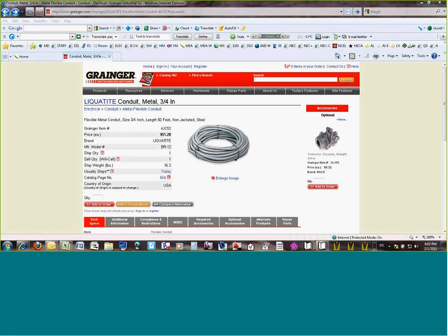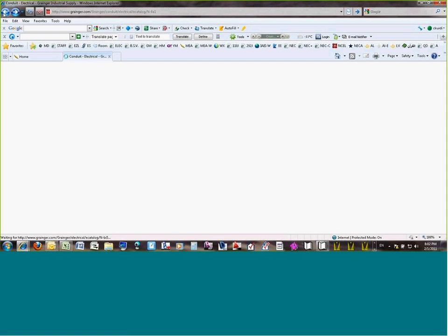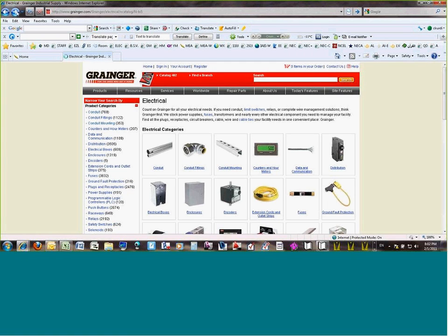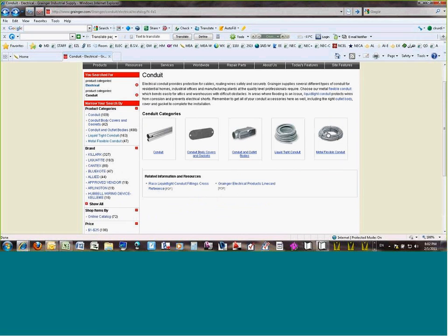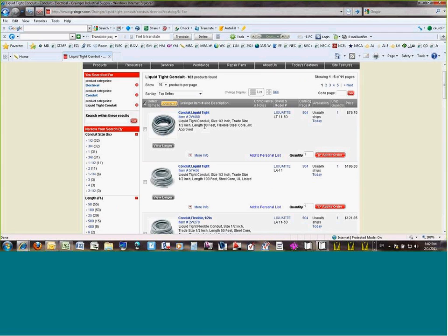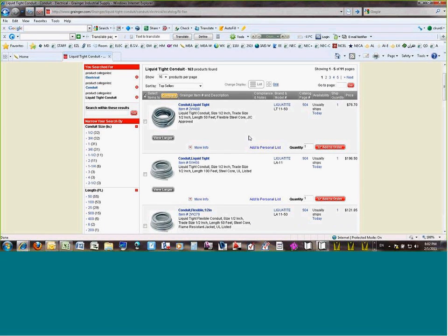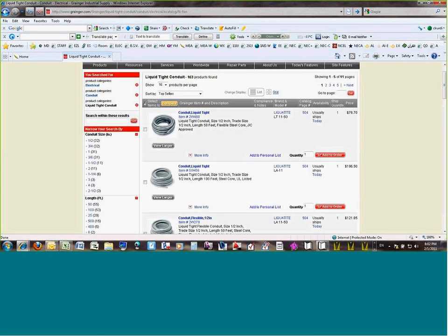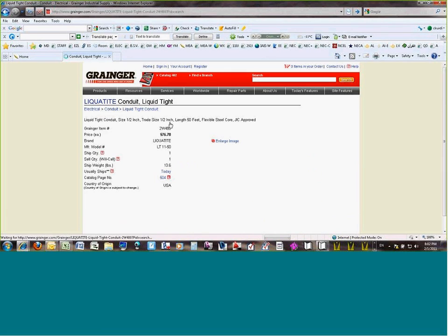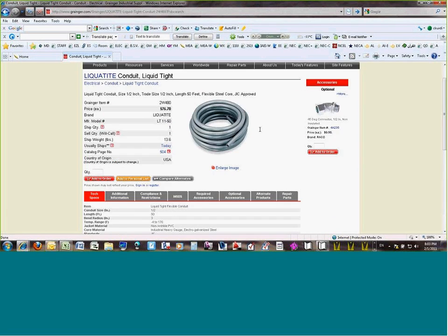Basically, let's go maneuver one more time, if you don't mind, and just go to Liquidtight. Okay, here, this is metallic. Here's Liquidtight, guys, and look at the material that they have for Liquidtight. Here's my Liquidtight metallic. This is Liquidtight conduit, size 1/2 inch, trade size 1/2 inch, length 50, flexible steel. So Liquidtight flexible steel conduit.